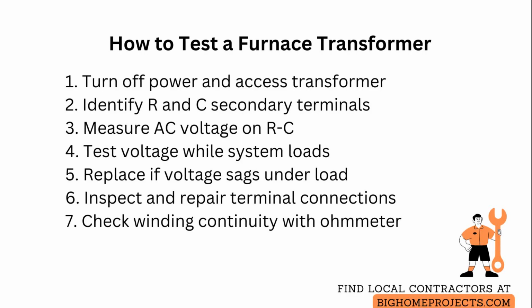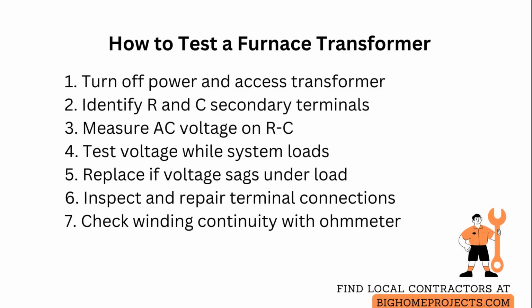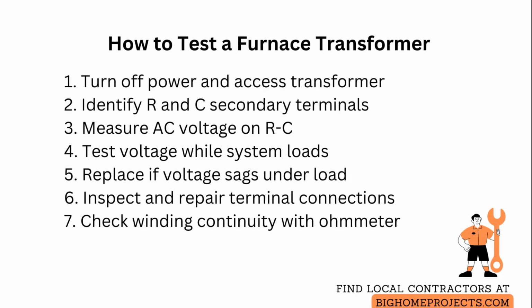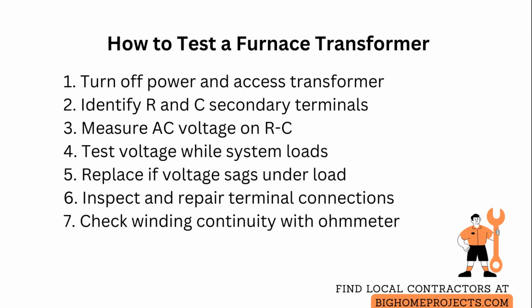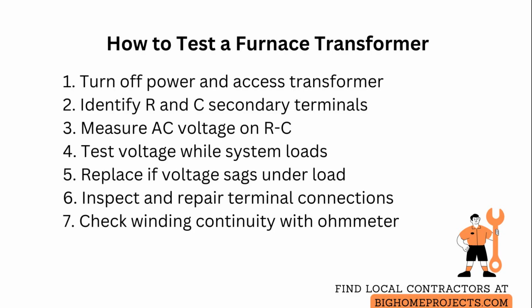chassis, with two primary leads connected to the line side and two secondary leads labeled R and C that feed the control circuit. If the transformer is the uncommon split winding style, identify the correct secondary pair before testing. With power restored and the thermostat calling for heat, set a digital multimeter to measure alternating current voltage on the secondary and place the probes on the R and C terminals.